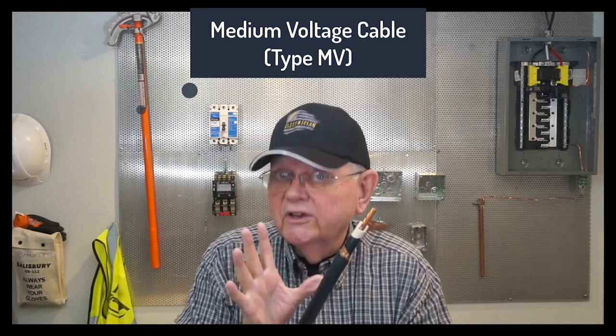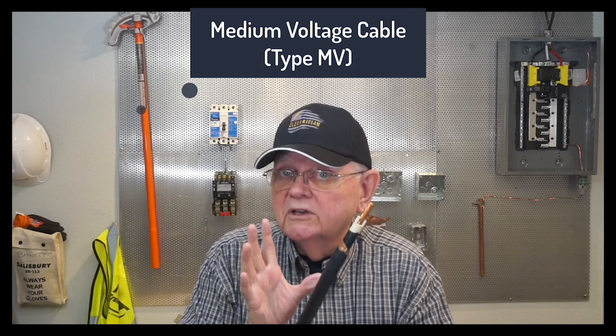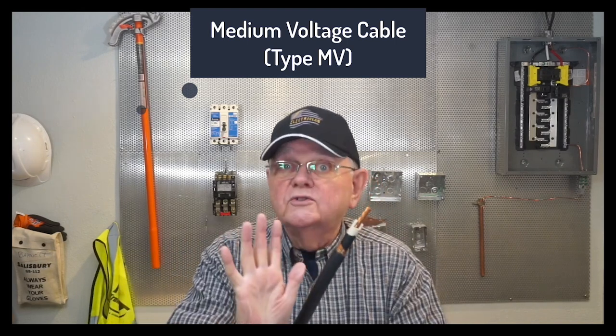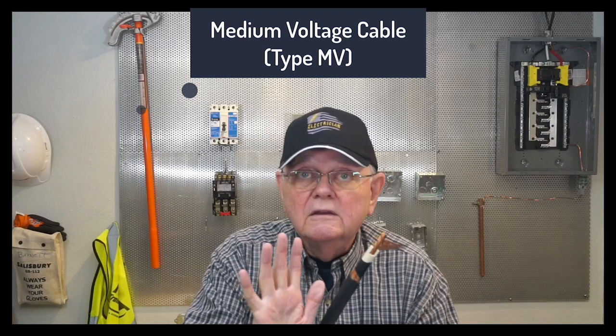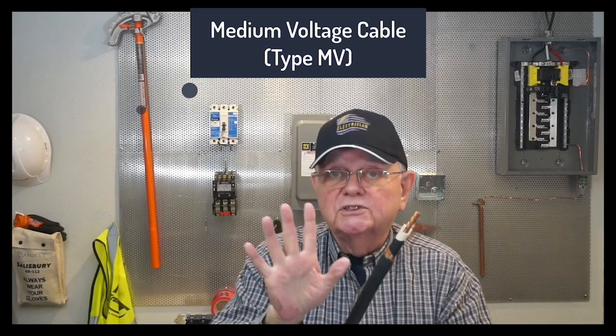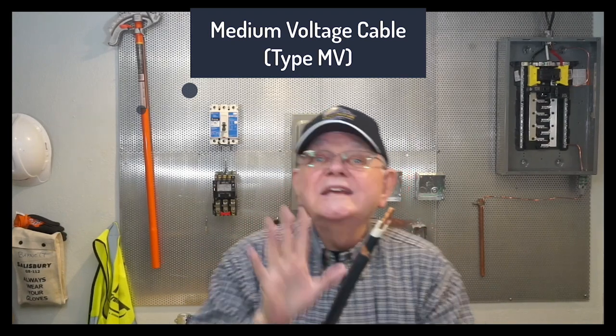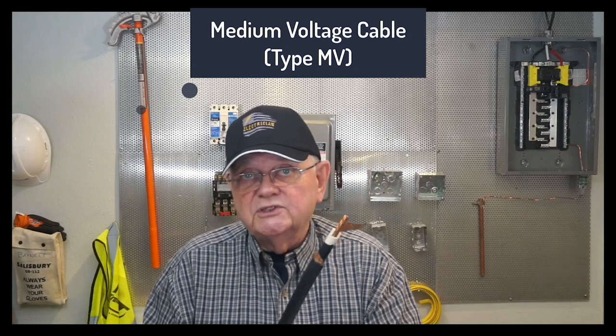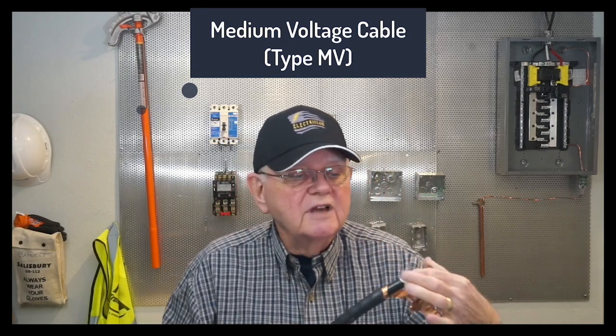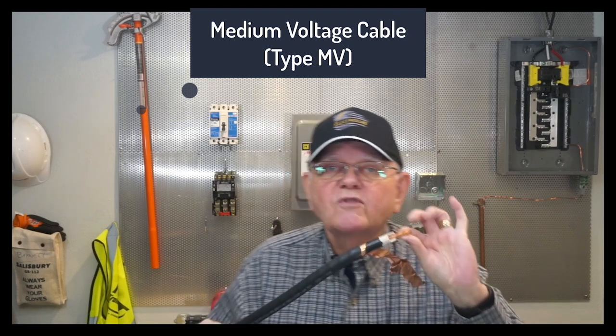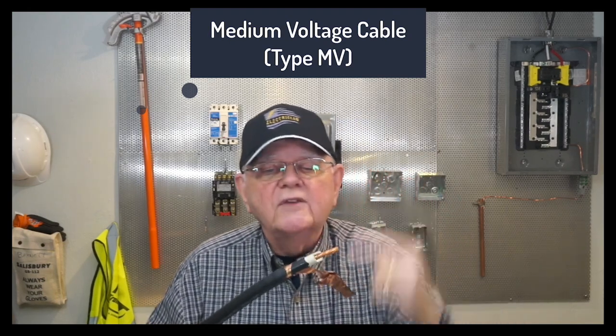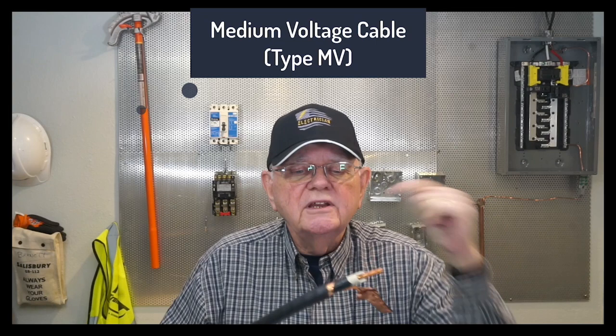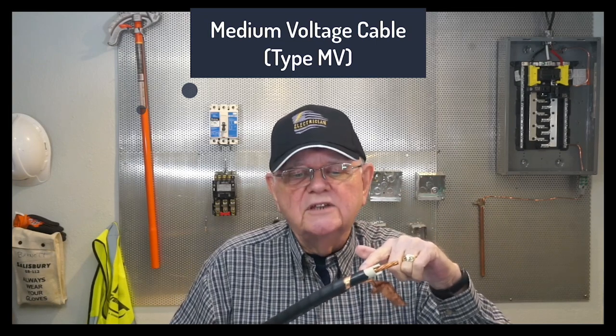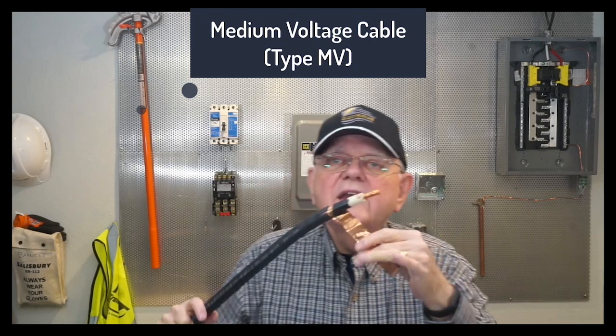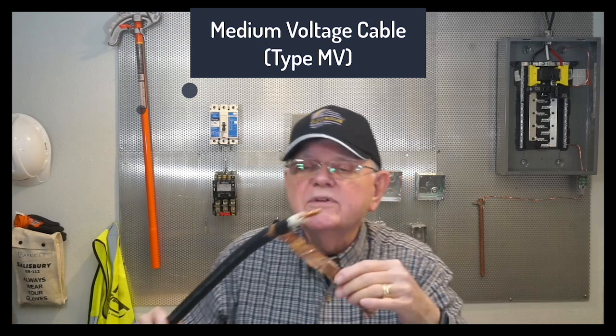Voltage is a pressure, isn't it? It's an electromotive force. And it's going to try and move molecules of insulation out of the way. It can punch through that insulation and so forth. So we need to relieve those voltage stresses. So we do that with a semiconductor layer, one that's extruded right over the copper conductor itself. Then there's the insulation, and then there's another semiconductor layer. Then I have the copper tape that's wrapped around the entire conductor.